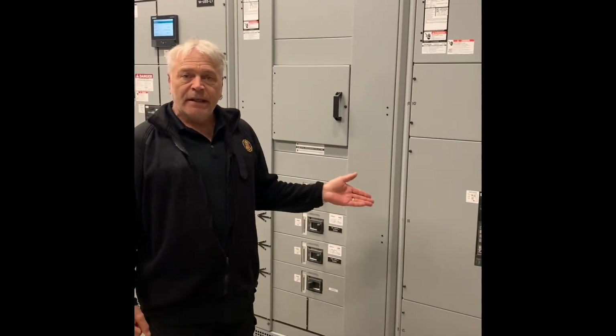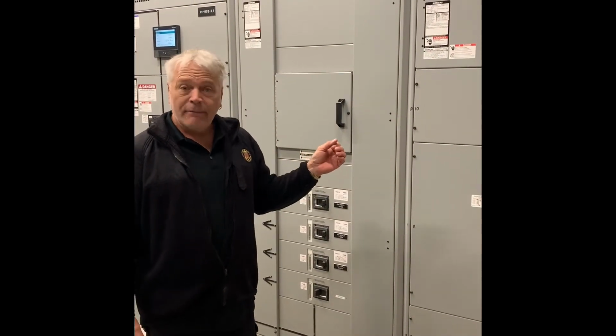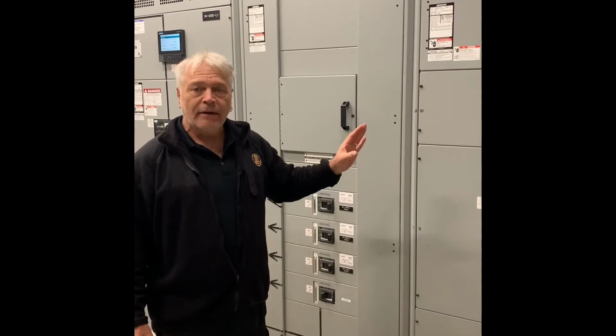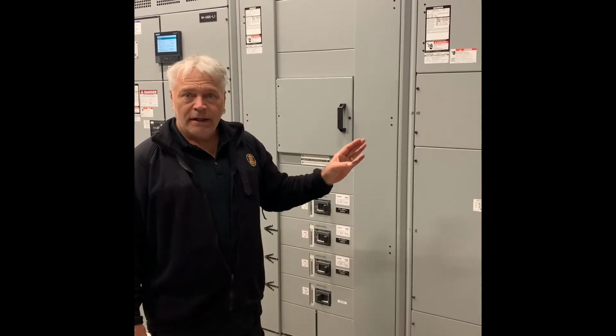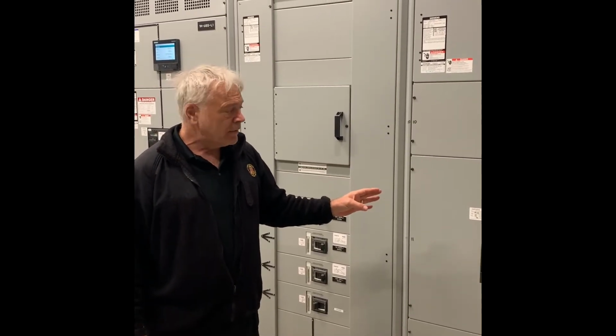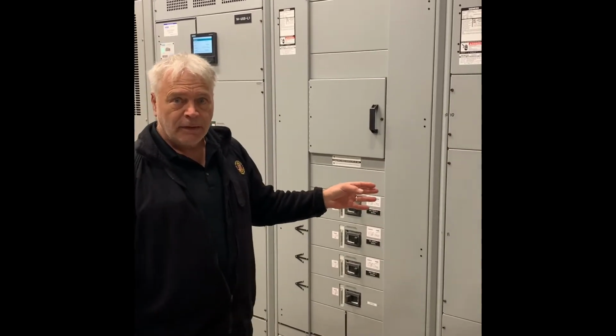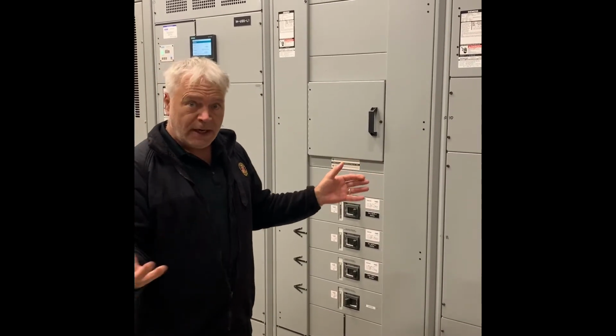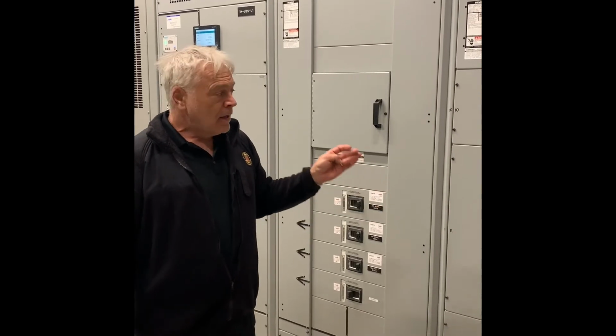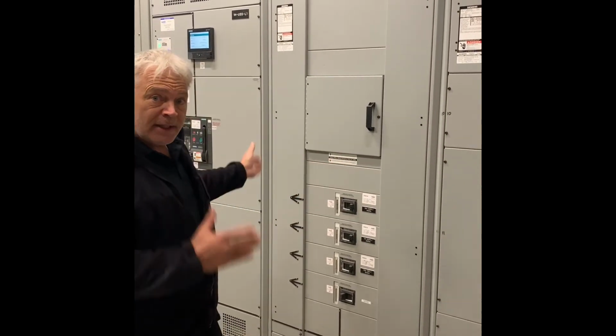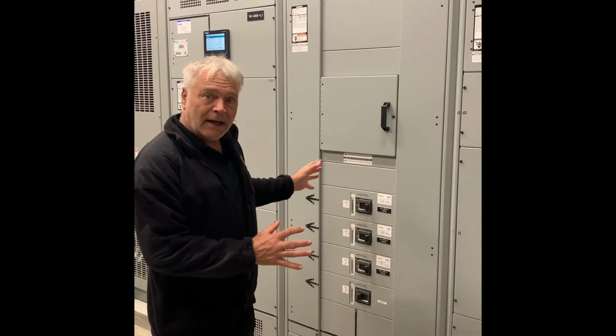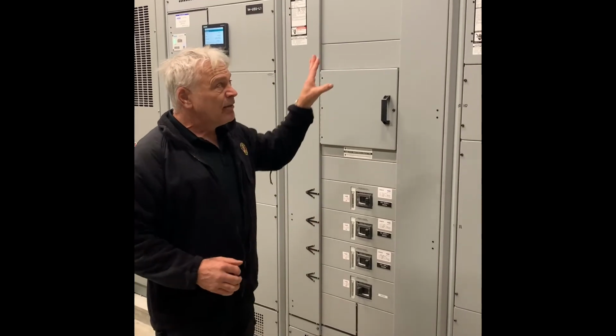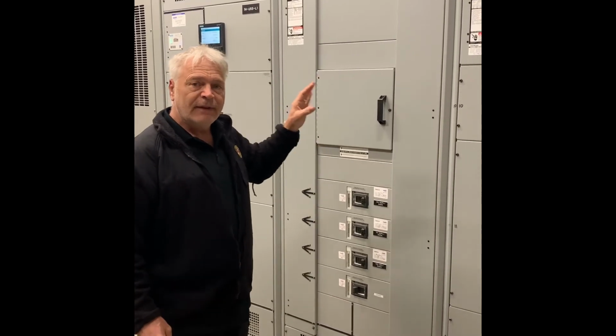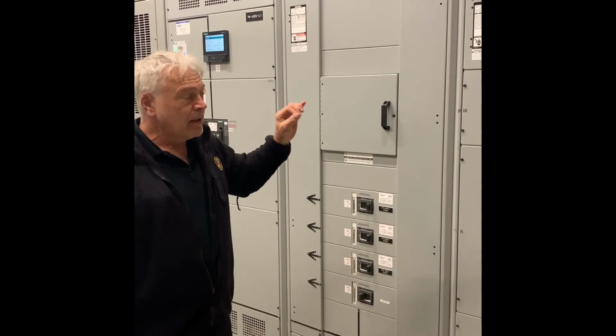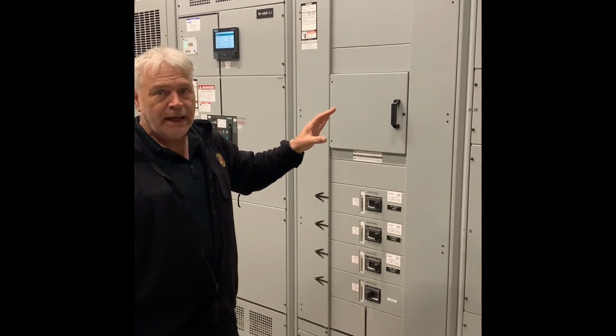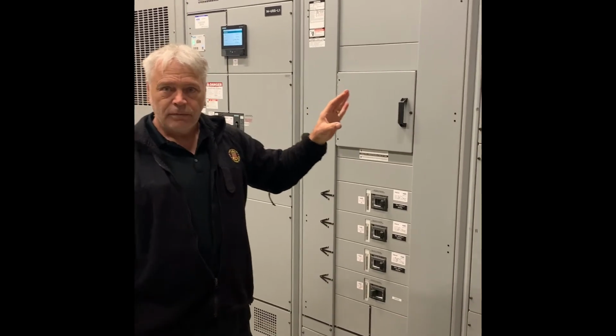Preventive maintenance should be done yearly. That recommendation is clearly laid out in the O&M manual, and the procedure is in the manual as well, and should be done by qualified people. You can hire that out, or if you train your guys to do it, they can do it as well. Normally, it requires a shutdown because you'll get inside and vacuum the dust out and verify the connections. All of the procedures and time intervals are clearly laid out in the O&M manuals, so refer to them.